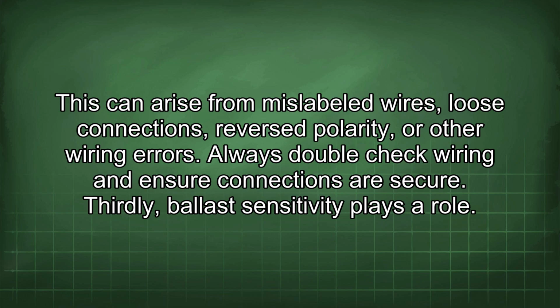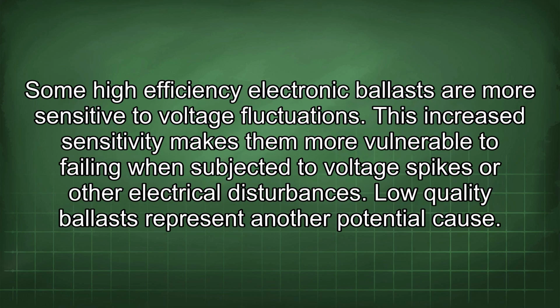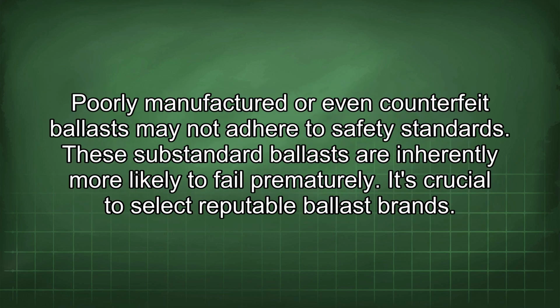Thirdly, ballast sensitivity plays a role. Some high-efficiency electronic ballasts are more sensitive to voltage fluctuations. This increased sensitivity makes them more vulnerable to failing when subjected to voltage spikes or other electrical disturbances. Low-quality ballasts represent another potential cause. Poorly manufactured or even counterfeit ballasts may not adhere to safety standards. These substandard ballasts are inherently more likely to fail prematurely. It's crucial to select reputable ballast brands.